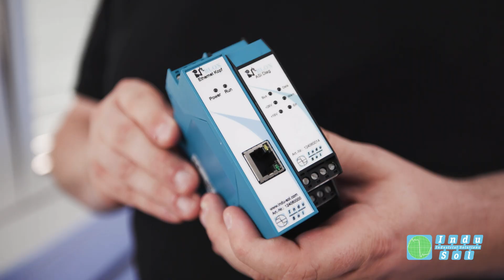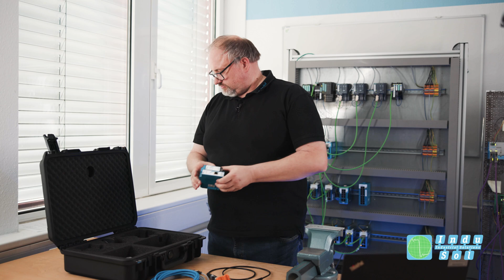The latest generation we have now is based on the IMBlocks. Here you would also connect it to the ASI system via the previously explained measuring point. All adapters are included in the case here as well. Here you have the connection adapter for the inspector, and since the whole thing can then be accessed via a web-based query, you also have a patch cable included. Otherwise, the inspector performs a continuous analysis of the telegram traffic, and here you can also see if you might have a bundle error, meaning faulty telegrams during operation, or if there is a voltage problem.